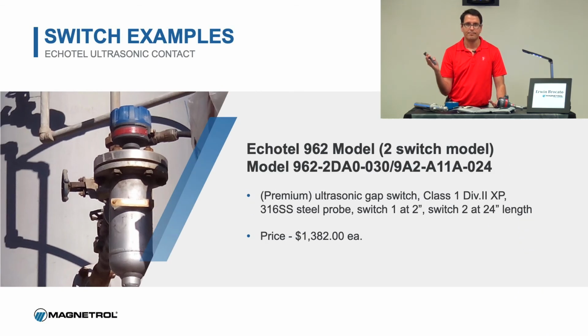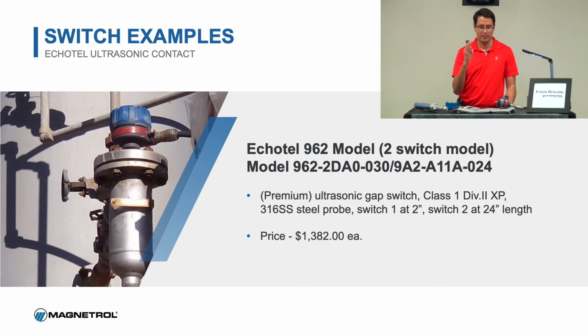Price points. The 962, so this is a stainless steel probe, Class 1 Div 2, explosion proof, is $1,300. This is basically a control, okay? You can control your level for $1,300. That's a fairly reasonable price in my opinion. It's not a transmitter. It's not going to give you any kind of trending feedback or anything like that. But you can do just a very, very simple control with one instrument in that chamber or bridle.